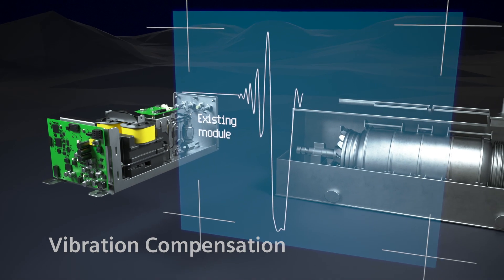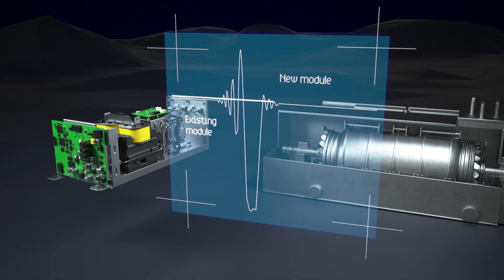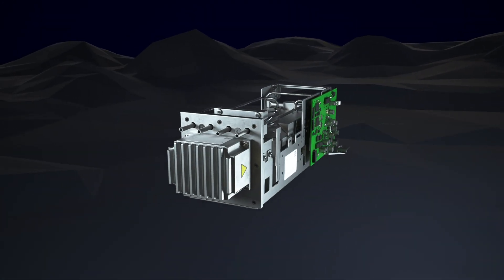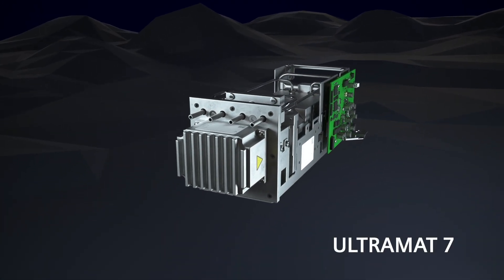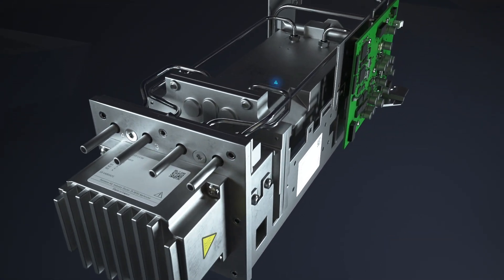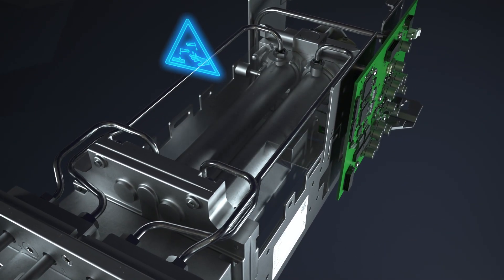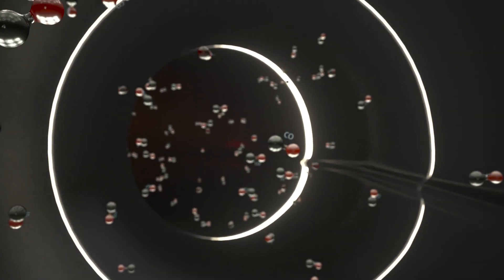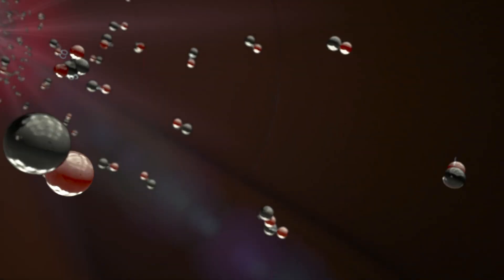For example, if measuring gases have a high water content or the system is deployed in harsh environments. Thanks to the materials selected for its gas-carrying parts, the new Ultramat 7 is also available for applications with corrosive measuring gases. A heated version is available for gases with a high water content.